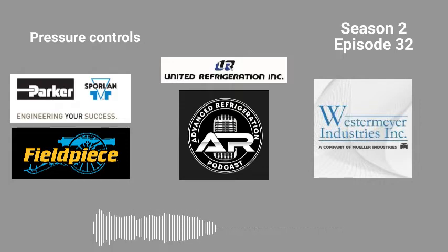It makes it a lot easier to set these in your van when you're not on a unit trying to constantly close and open the suction to set a low pressure control. So that's why I like to do it on nitrogen — it's a lot easier, less stressful. Say it's 4 p.m. on a Friday: you could set this low pressure control in your van real quick with nitrogen, test it one or two times, adjust it where you need it, throw it on the roof, test it once to make sure it kills the compressor, and you're good to go.